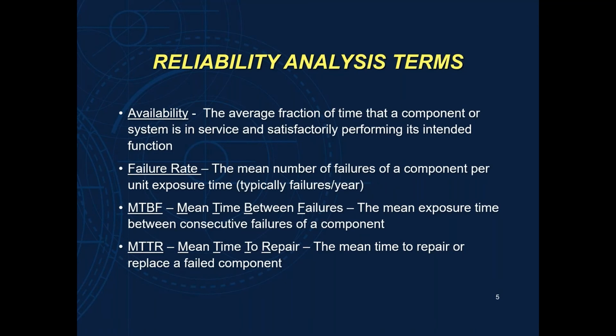So here's some terms that we're going to talk about. Availability. So reliability, the word reliability is the exact opposite of probability of failure. So if you have a 10% probability of failure, we would say that you have a 90% reliability factor in your system. Availability is a little different because availability takes that reliability factor and adds in downtime to determine how much in a percentage of time your system will be available to provide sufficient power to your operation.